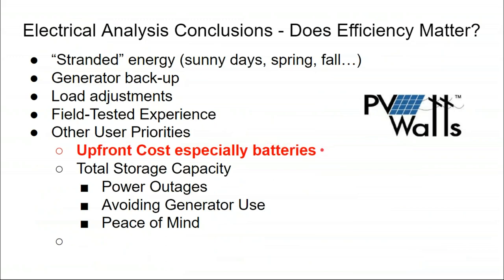The upfront cost of batteries is going to be the biggest stumbling block. A lot of the content in today's program is going to be focused on lead acid batteries. I've actually started to change my design philosophy, which has always been heavy on industrial flooded lead acid for value. At this point, I'm giving stronger consideration to used lithium ion for off-grid applications, because it's cheaper than new lead acid, and you buy new lead acid because of reduced upfront cost. There's some good pros to it, there's also some cons to it. You take the good with the bad.